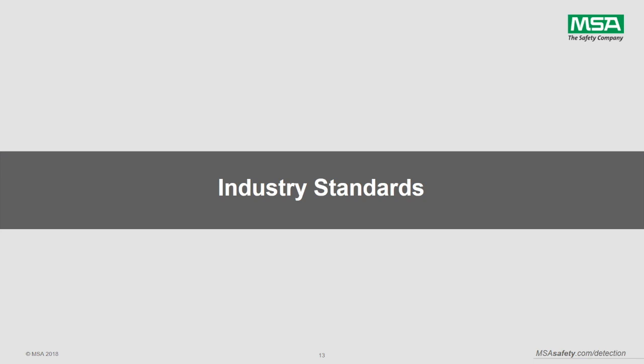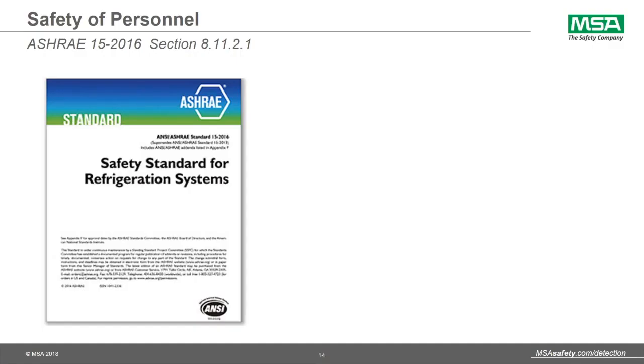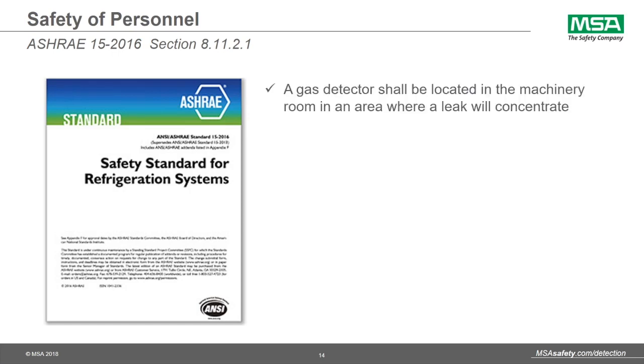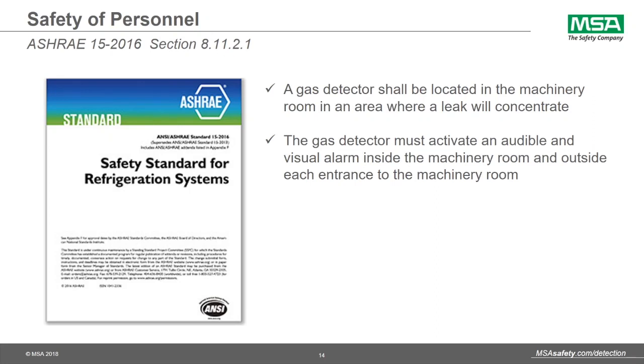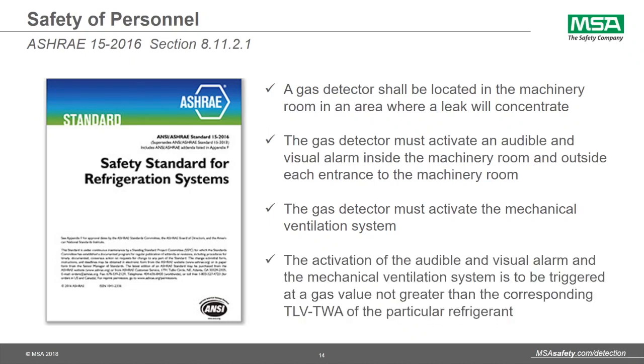And this brings us to current industry standards. The standard that most drives refrigerant leak detection in mechanical rooms is ASHRAE 15, section 8.11.2.1. ASHRAE 15 is a safety standard that is more directive towards personnel safety. And ASHRAE states, a gas detector shall be located in the machinery room in an area where a leak will concentrate. The gas detector must activate an audible and visual alarm inside the machinery room and outside each entrance to the machinery room. The gas detector must activate the mechanical ventilation system, and the activation of the audible and visual alarm and the mechanical ventilation system is to be triggered at the gas value no greater than the corresponding TLV, TWA of the particular refrigerant.